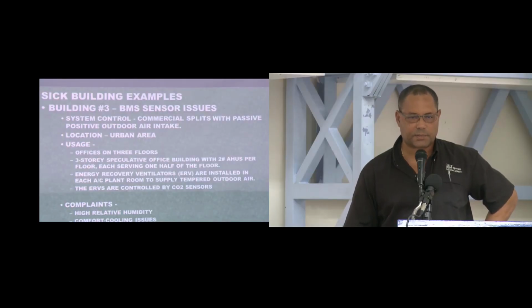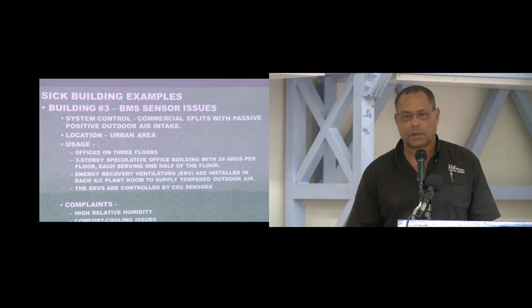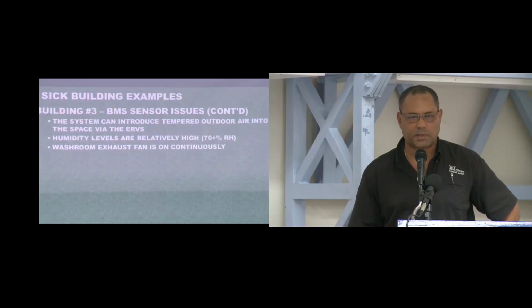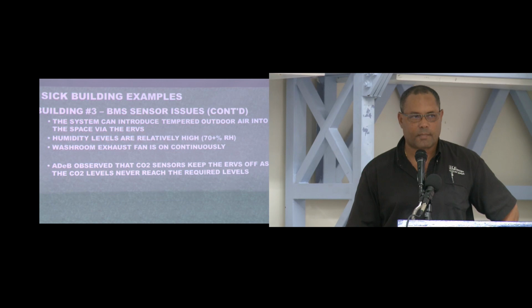Well, they've got high relative humidity issues, comfort cooling issues. So people complain about being warm, too cold, humidity is up in the 70s, nobody's happy. So you've got this system set up to introduce tempered outdoor air into the space through the ERVs. Your washroom exhaust fan is on continuously, which means whether the ERVs are working or not, air is being exhausted. Again, if you're exhausting continuously, the air's got to be coming from somewhere. So infiltration is preventing the CO2 levels from rising to the point where they trigger the ERVs.